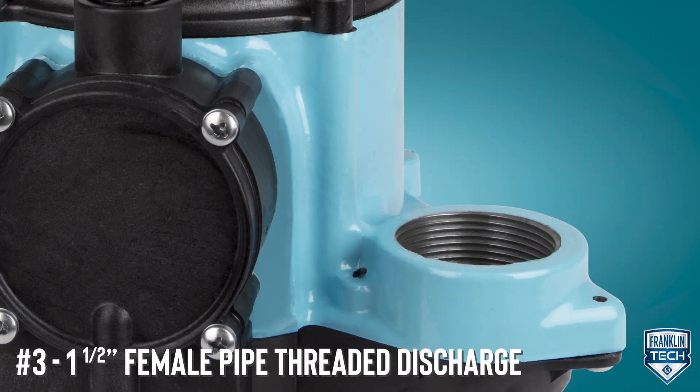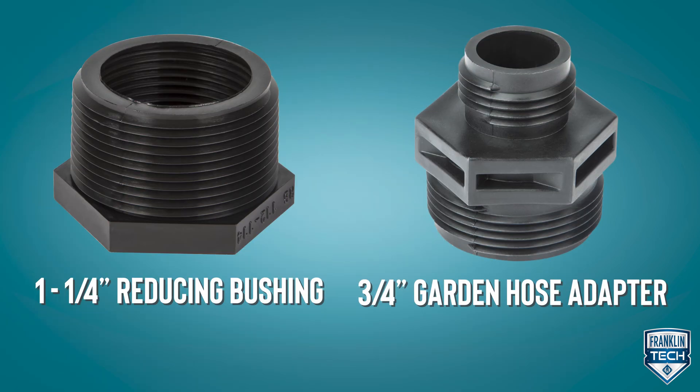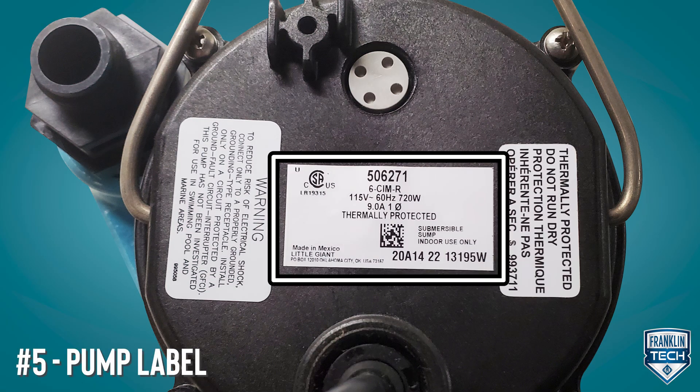The pump comes with a standard 1.5 inch female pipe thread discharge, while the manual version also includes a 1.25 inch reducer bushing and a 3/4 inch garden hose adapter. The cord is available in multiple cord lengths to suit semi-mobile or permanent installations. Reference the voltage requirements on the pump label to connect the pump to an appropriate power supply.